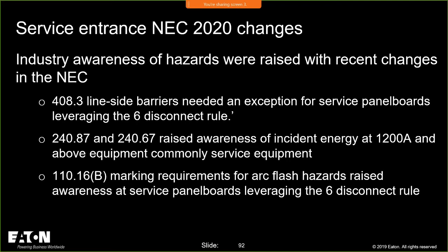So what they did was they put an exception in, and then that caused people to start thinking. That was really the driving factor, because they said, wait a second, we're worried about the electrical worker on this equipment that is at the service entrance, but I'm not going to worry about it if it's using the 6 disconnect rule, which is even less, has more of an issue. So that raised the awareness, and to you individuals who made some public inputs to make a change to the 6 disconnect rule, which we're going to talk about.